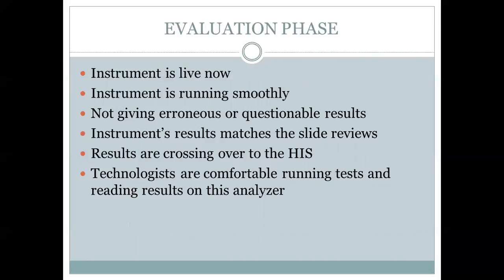So after the training was done, we were in the evaluation phase. So now the instrument is live. We can start using it, and then it will give us results, and we can verify those results. We want to evaluate that the instrument is working fine, running smoothly, not giving us any questionable or erroneous results. If we see a questionable result, we will evaluate the sample to see if there was any problem with the sample. Suppose the sample was drawn from the arm where there was a line, and then we got contamination in the sample. So we want to make sure that the erroneous result that we got was not because of the instrument, but because of the sample itself.